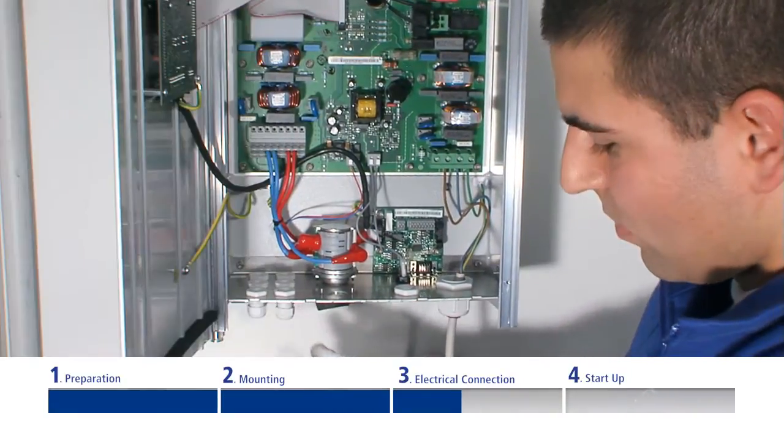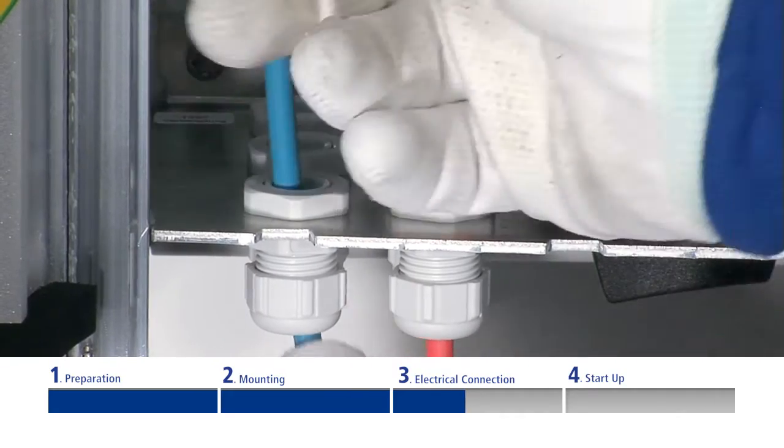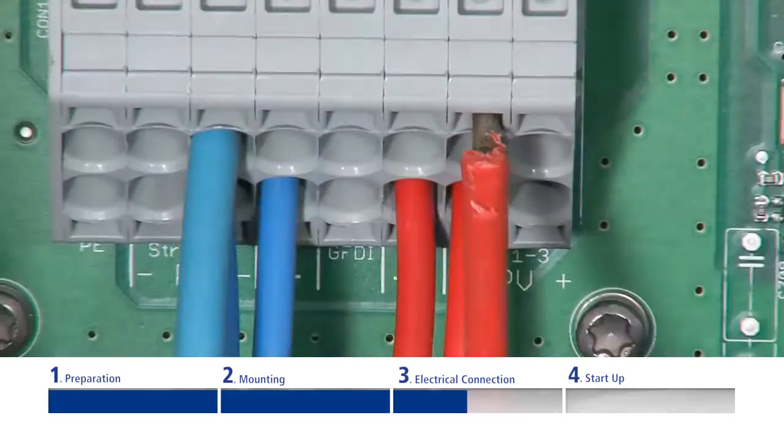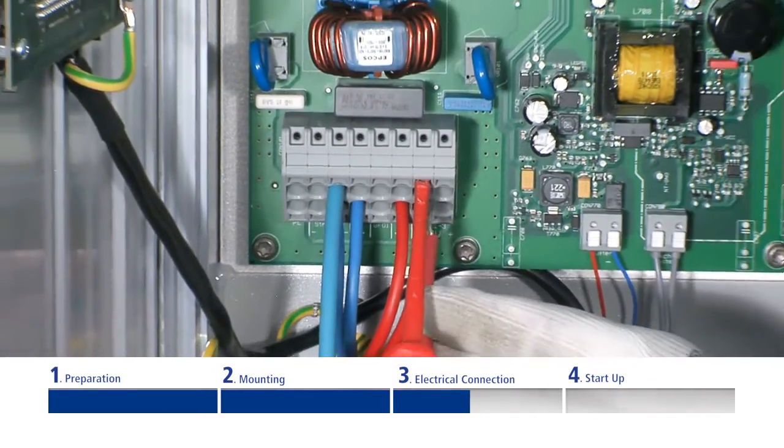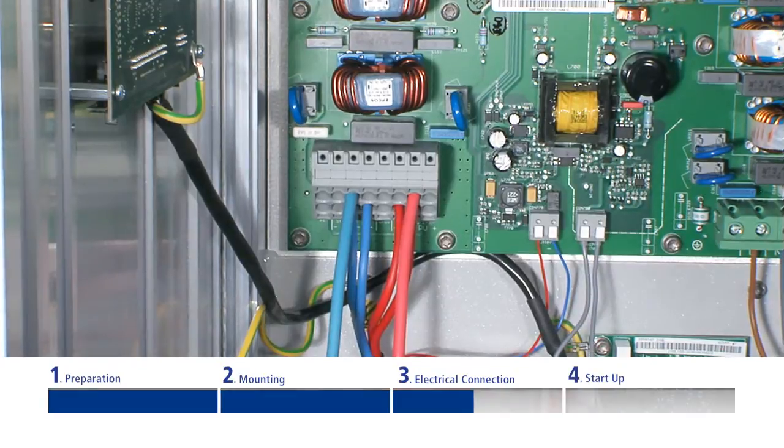Secure the cable ends into the connection terminals. Pay attention to the PV plus and PV minus signs. Connecting to the wrong pole will damage the inverter. Tighten the cap of the cable fitting.